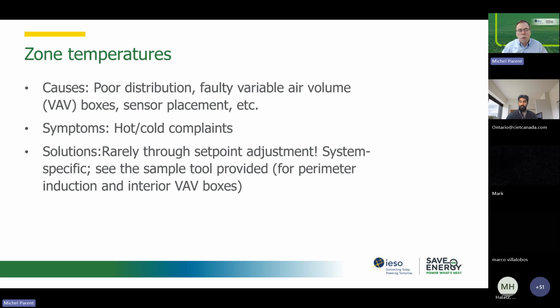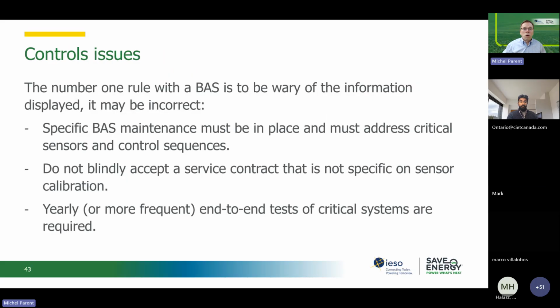So if you've got a real issue with pressure, your first course of action is to go after the building envelope. For the zone temperatures, it's the tool that I showed you that we're going to provide you, along with a possible functional test you could do once a year to identify the boxes that need to be looked after and resolved where there are issues. If you've got an FDD, a fault detection and diagnostic system, it will likely provide you the same kind of information, if the FDD is well commissioned and working properly, which is a big if. So that brings us to control issues.